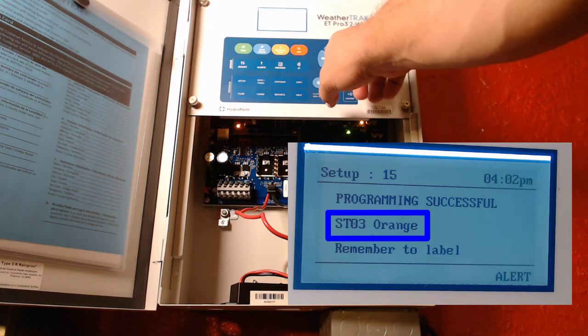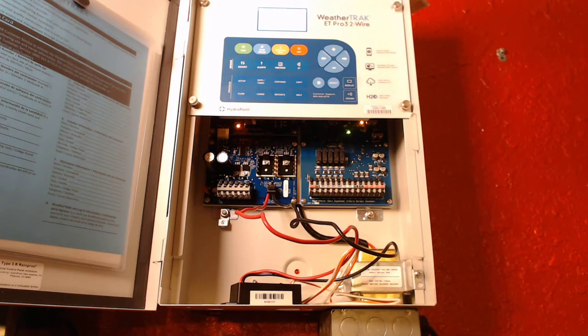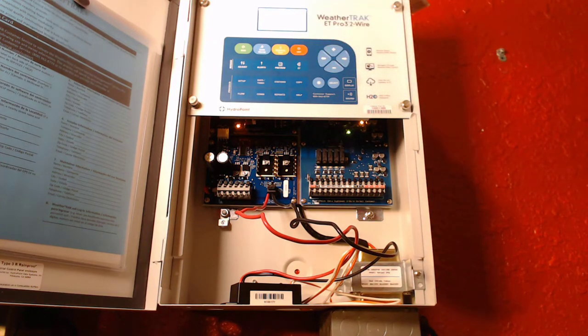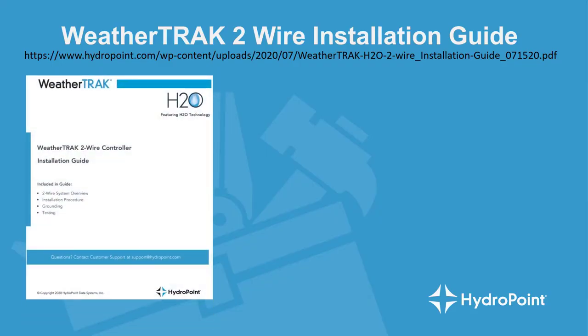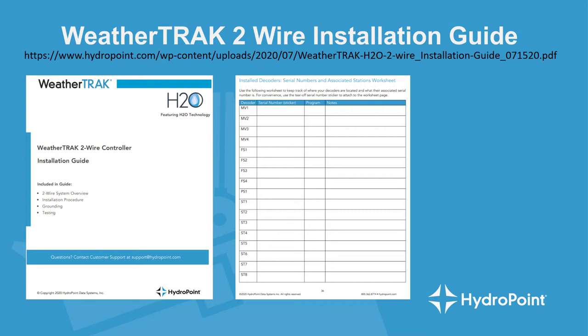The orange wire is associated with that station, which becomes important with dual decoders where you need to differentiate which hot wire goes to which valve. Label the decoder and unplug it from the station program terminal. A couple of pro tips: labeling your decoders is key — immediately and clearly label them to avoid duplicate decoders with the same address on the system. Also, always properly document where the decoders are to minimize troubleshooting in the future. Download the WeatherTRAK two-wire installation guide, which includes a handy worksheet to document each decoder, its serial number, and other vital information.